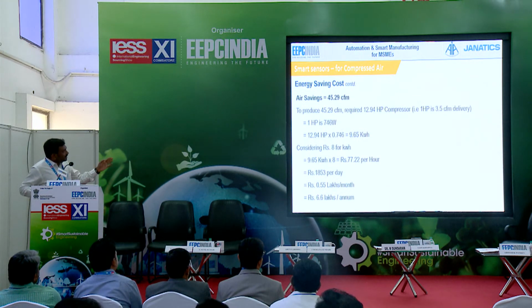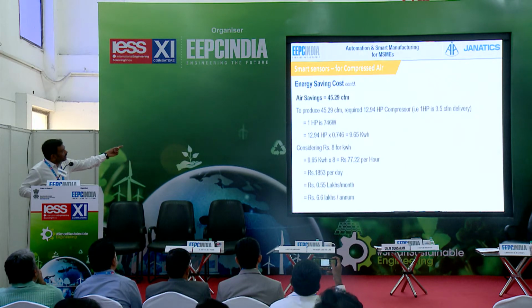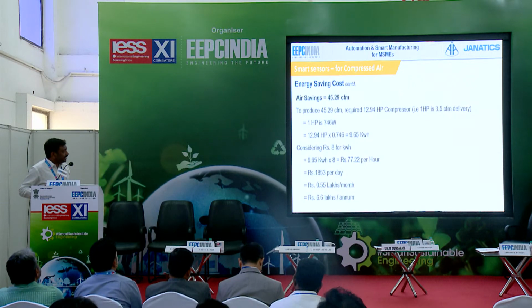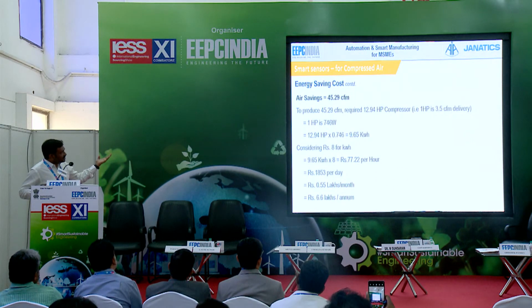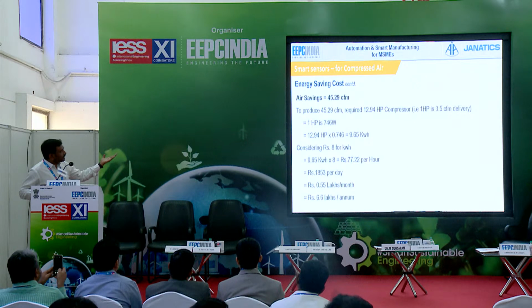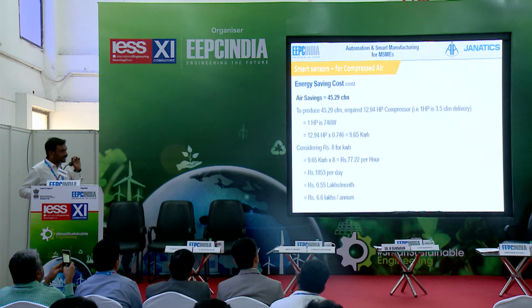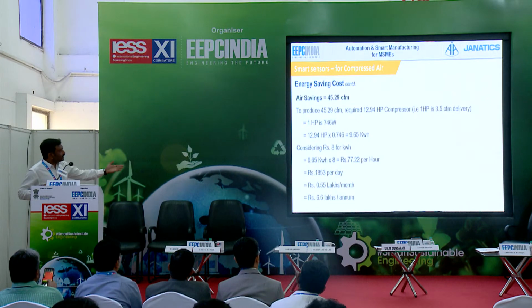To understand the cost to produce 45 CFM: it requires a 12.9 HP compressor to produce that much air. For 1 HP it's 746 watts. Calculating with respect to that, it comes close to 9.65 kilowatt hours. Considering 8 rupees per kilowatt hour, you can save 6.6 lakhs per annum.